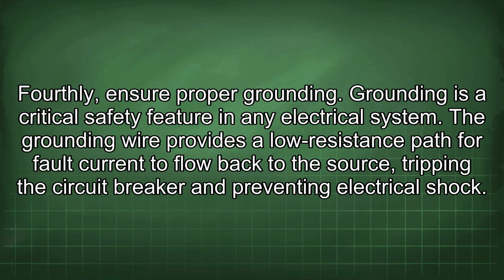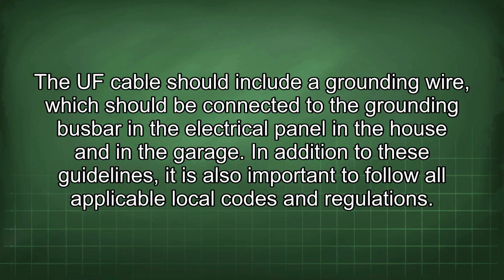Fourthly, ensure proper grounding. Grounding is a critical safety feature in any electrical system. The grounding wire provides a low resistance path for fault current to flow back to the source, tripping the circuit breaker and preventing electrical shock. The UF cable should include a grounding wire, which should be connected to the grounding busbar in the electrical panel in the house and in the garage.